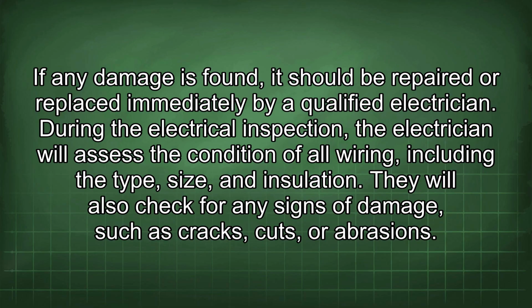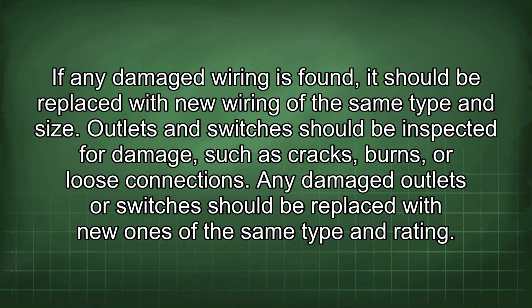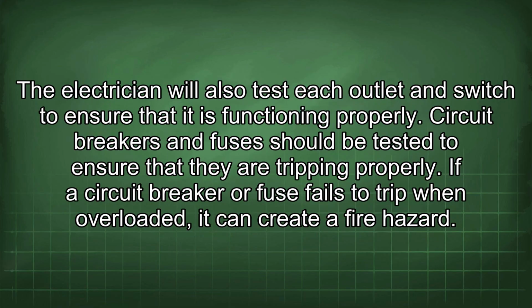During the electrical inspection, the electrician will assess the condition of all wiring, including the type, size, and insulation. They will also check for any signs of damage, such as cracks, cuts, or abrasions. If any damaged wiring is found, it should be replaced with new wiring of the same type and size. Outlets and switches should be inspected for damage, such as cracks, burns, or loose connections. Any damaged outlets or switches should be replaced with new ones of the same type and rating. The electrician will also test each outlet and switch to ensure that it is functioning properly.